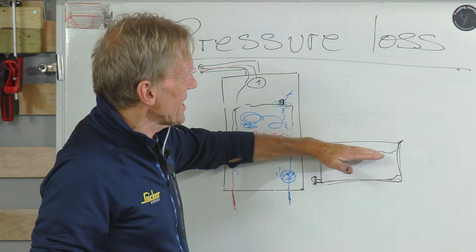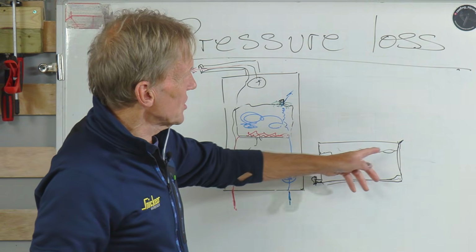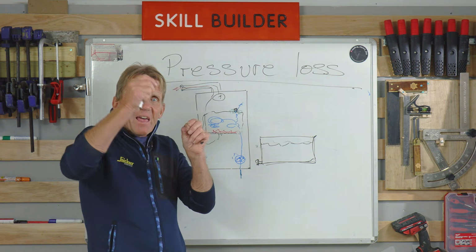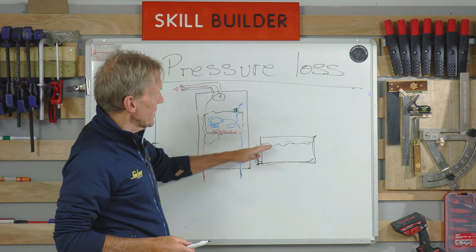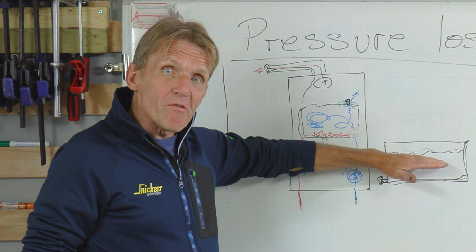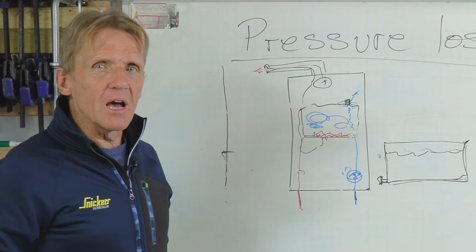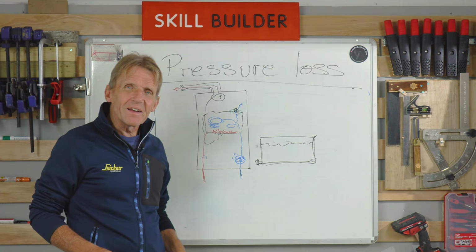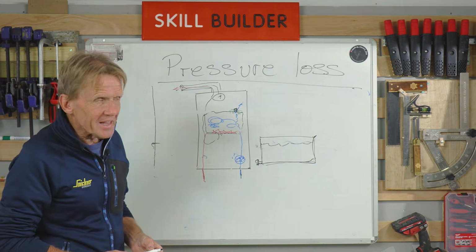The hydrogen gas is collecting in the top of the radiator there, and a lot of plumbers will do this: relieve the valve slightly, put a match or a cigarette lighter to it, and you can see a little flame coming out where the hydrogen is being burnt off. I'm not suggesting you do that, but it is a fact that it can do that. So if it's hydrogen that's coming out of there, it's because your radiators, your towel rail, whatever else it is, are rusting away. And you very often find that the free hydrogen gas collects in one radiator particularly. That's usually a radiator that's first on the system at the top of the system, so a bathroom towel rail would be a very likely candidate for that to happen.